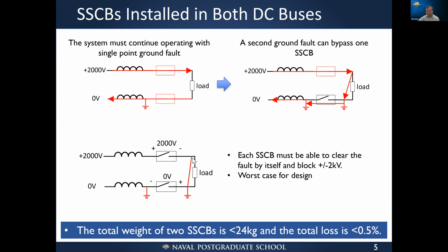Of course, after the fault is cleared, if the short circuit fault is still there, then these breakers need to withstand the full DC link voltage, 2 kilovolts in this case, like plus and minus, right? It depends on the location. So each solid state breaker must be able to clear the fault by itself and block plus minus 2 kilovolts. This is the worst case for the design. So in the design, we only design the solid state circuit breakers to handle the fault by themselves. And later on, if we have both working together to clear the fault, it's only easier. Right? And that also means the total weight of the 2 solid state breakers is less than 24 kilograms, or each one of them must be less than 12 kilograms. And the total loss is 0.5%. Okay, just keep that in mind.